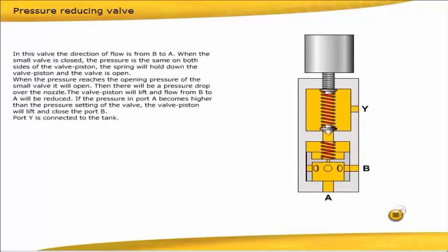In this valve, the direction of flow is from B to A. When the small valve is closed, the pressure is the same on both sides of the valve piston. The spring will hold down the valve piston and the valve is open.